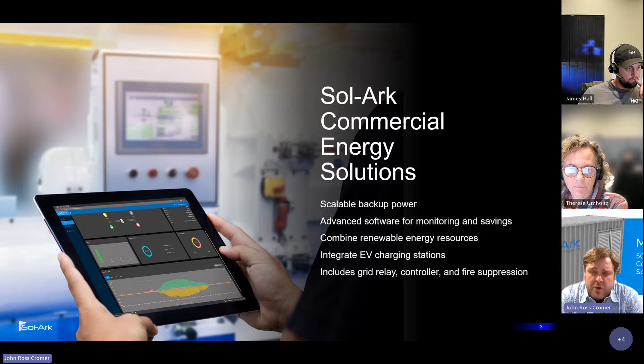Some differences between our commercial line and our residential line are opening up new applications that you might not have thought about for Sol-ark before. The first would be very large commercial rooftop solar arrays, and the Sol-ark inverters can handle DC coupling and landing the solar array directly onto the inverter, and that DC coupling is usually a very cost-effective strategy. But there is an advantage to AC coupling that the Sol-ark platform uniquely has within its commercial product line, which I have yet to find on any other commercial inverter system. And so it's good to know about.